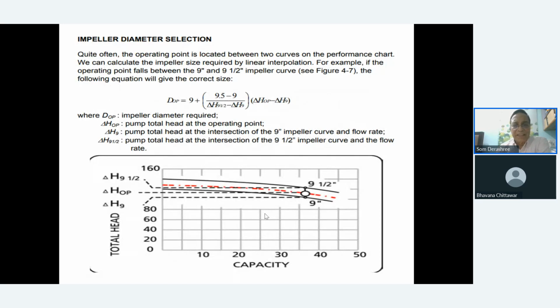So for impeller diameter selection, let's say you have 9.5 and this 9 inches, but your application is somewhere here, for example. How do you calculate that? Very simple. It's interpolation. This is just a formula for interpolation. This side is the delta H, and this side is the diameter of the impeller. So 9 is the minimum, plus you add 9.5 minus 9, divided by the head difference, compared to the operating head minus H at 9. So from here you will come somewhere around here, and you will get the diameter of the impeller that you would need.